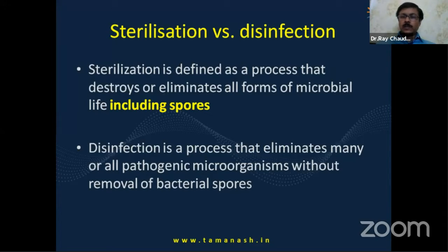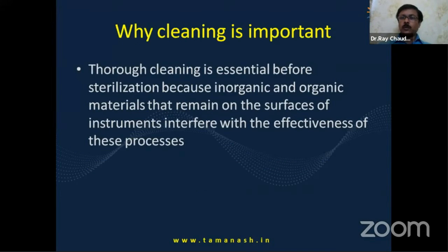Sterilization versus disinfection. We hear a lot about disinfection nowadays in COVID times, but sterilization means removal of all microbes, meaning bacteria, fungi, viruses, parasites, everything, including spores. Whereas disinfection usually eliminates the majority of pathogenic organisms but does not remove spores. So that is an important distinction, and we will be talking only about sterilization in this talk. So why is cleaning important? As I said, if the instruments are covered with dirt, then the effectiveness of the sterilization process will be low.